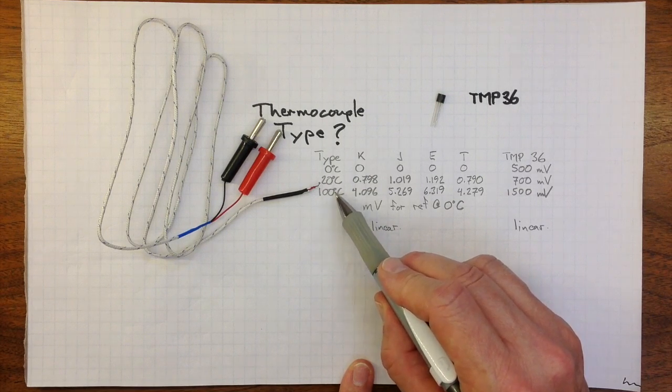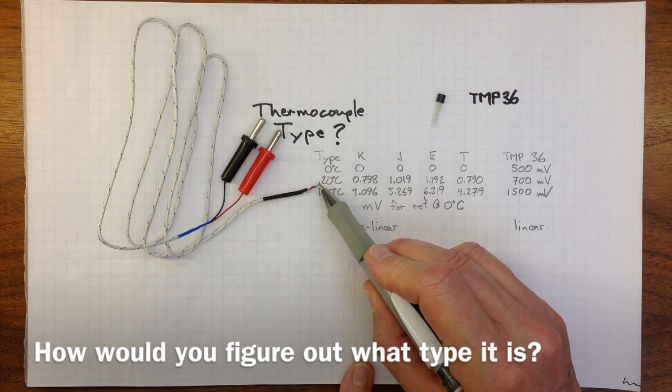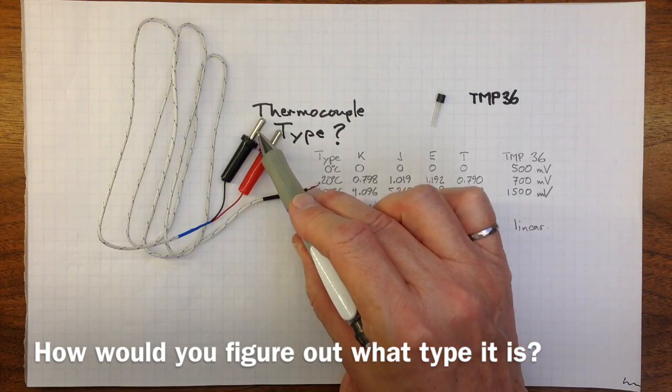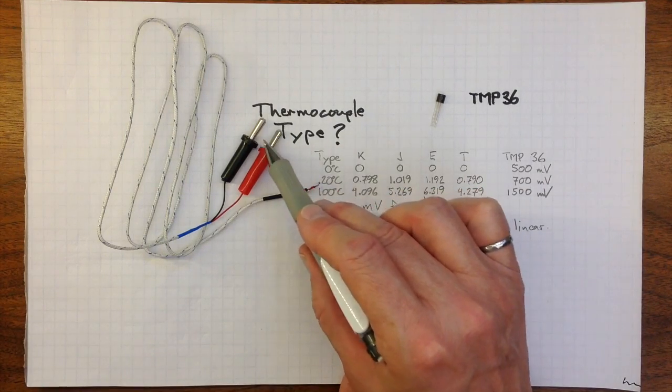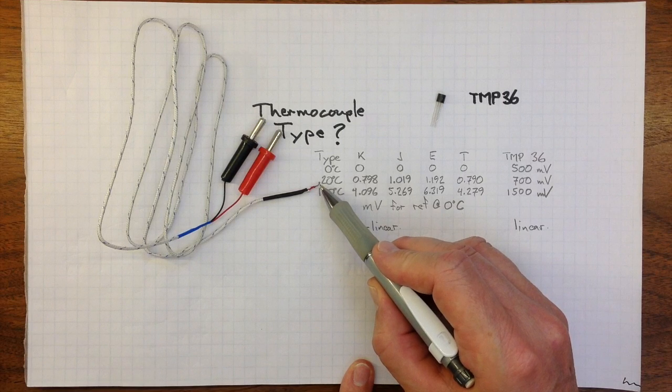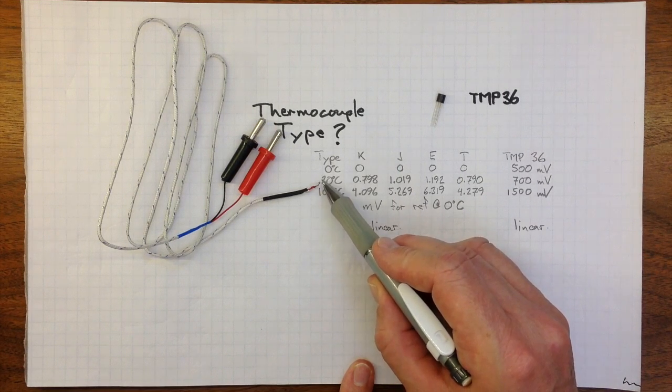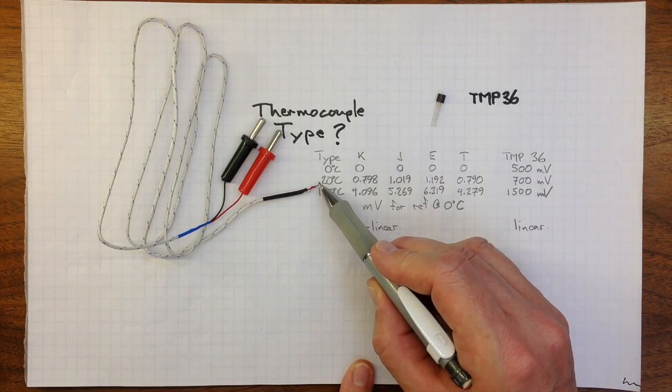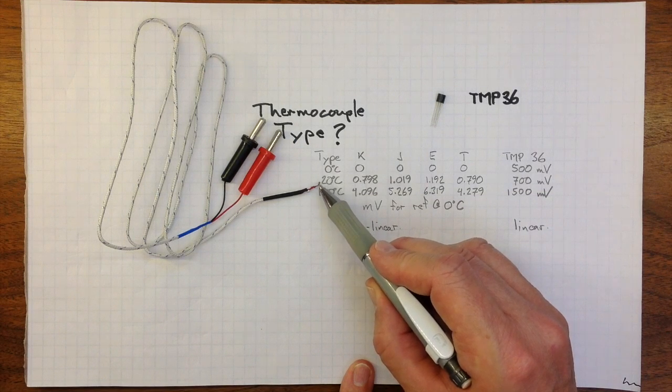The key thing here is it's the temperature of the bead that determines what the voltage is that we'll see on those two wires there. So it's not the temperature of the air around the bead, it's the temperature of the actual junction, the temperature of the actual transducer.